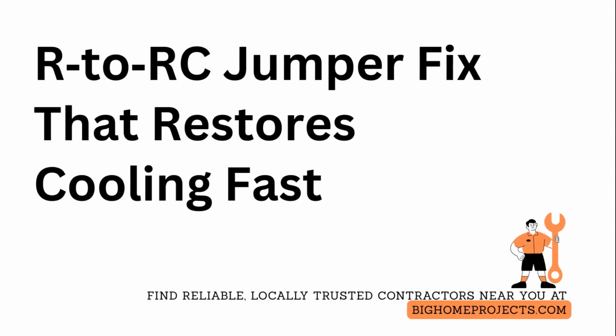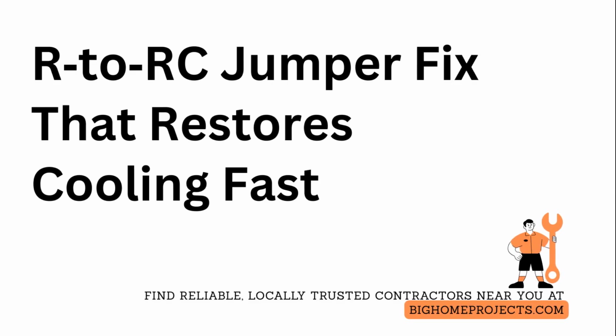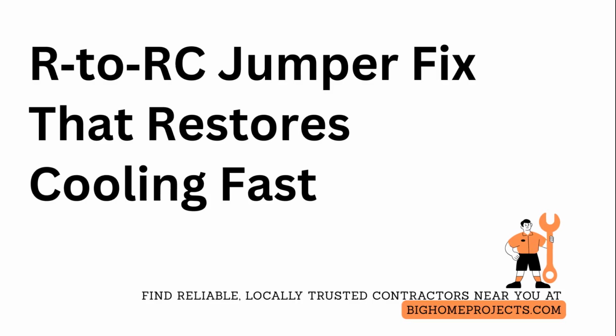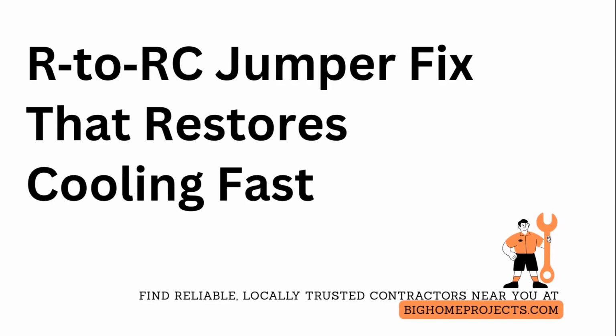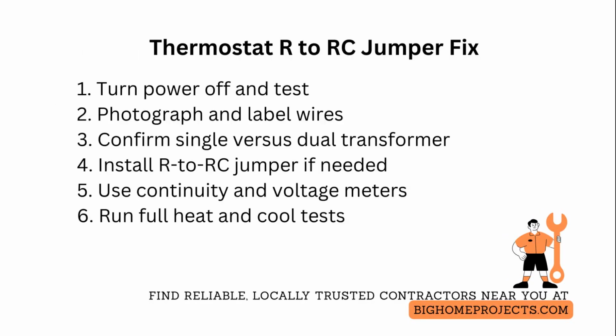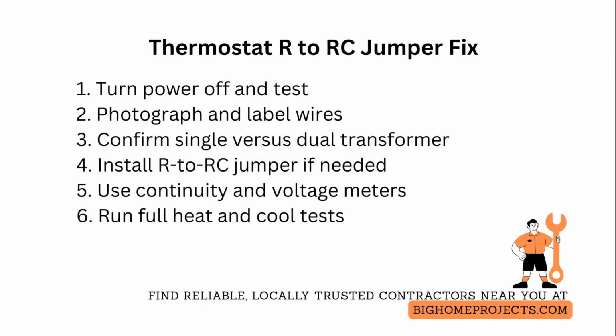Upgrade your thermostat without losing heat or cool. Missing the jumper between R and RC on a single system setup can quietly disable one mode. When wiring a single-zone heating and cooling system, treat the R and RC terminals as siblings that often need a jumper to feed both the thermostat's heating and cooling circuits.